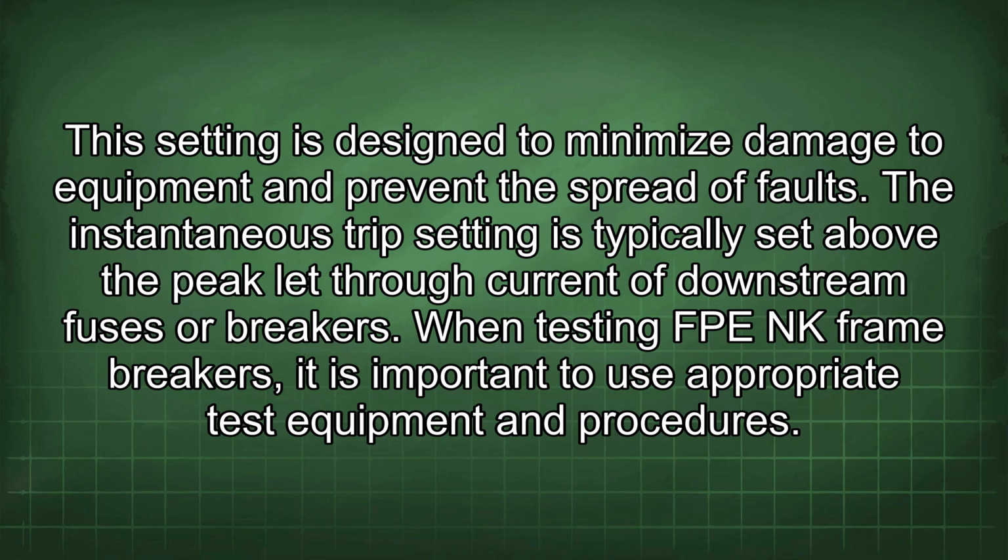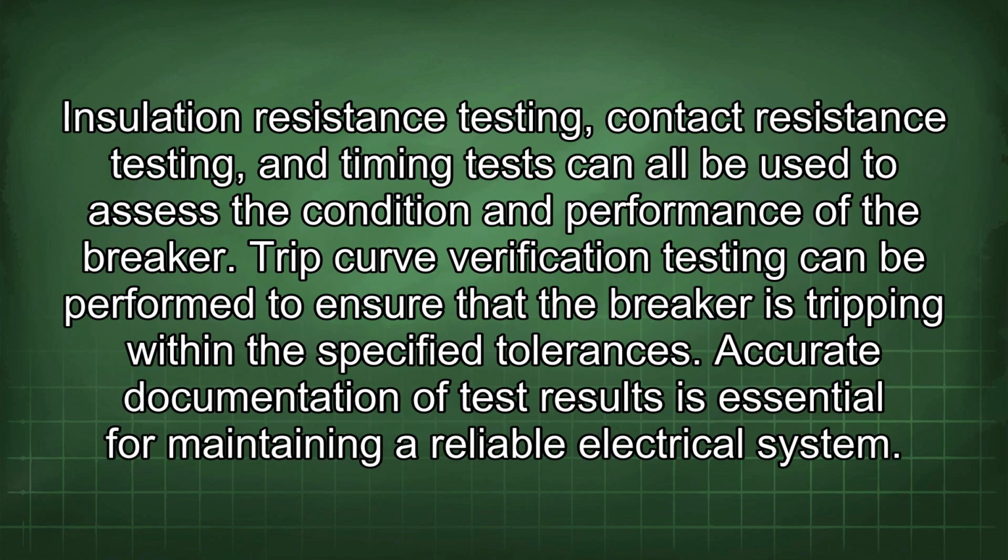When testing FPE NK frame breakers, it is important to use appropriate test equipment and procedures. Insulation resistance testing, contact resistance testing, and timing tests can all be used to assess the condition and performance of the breaker. Trip curve verification testing can be performed to ensure that the breaker is tripping within the specified tolerances. Accurate documentation of test results is essential for maintaining a reliable electrical system.